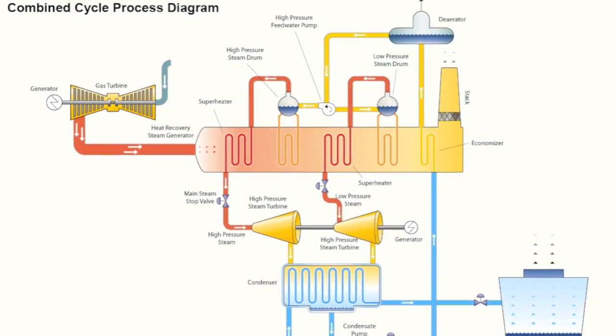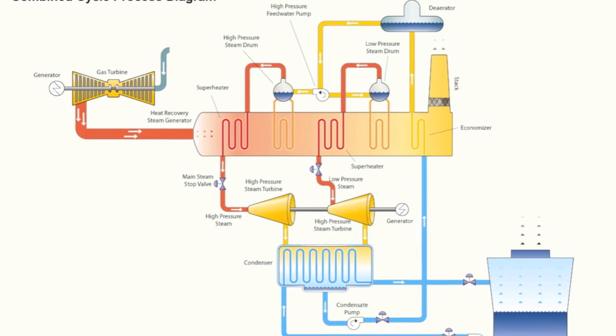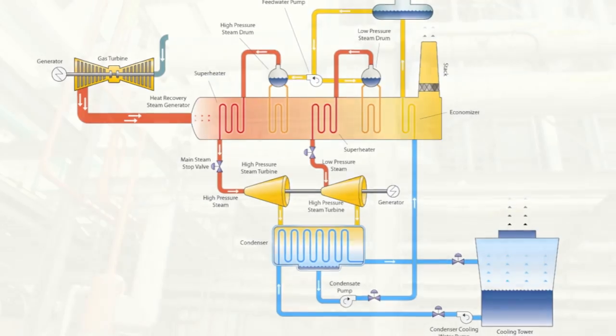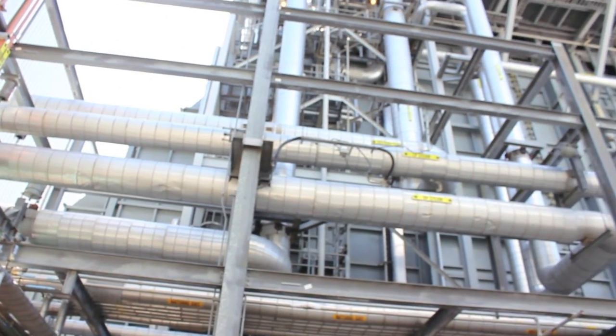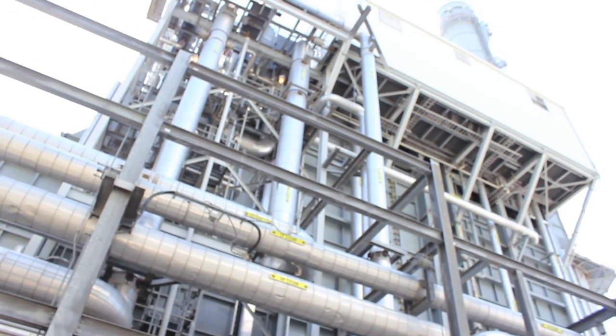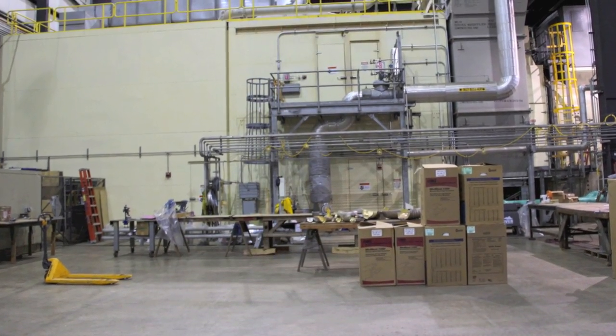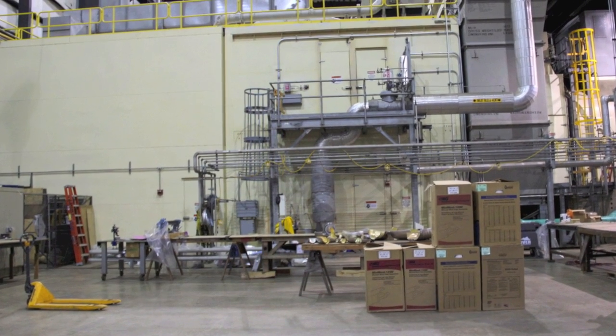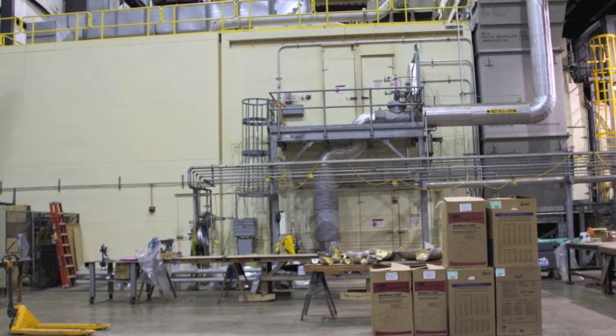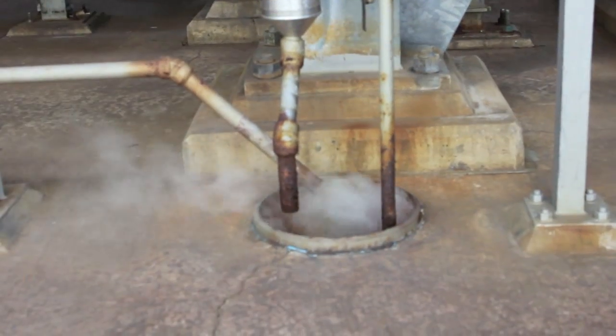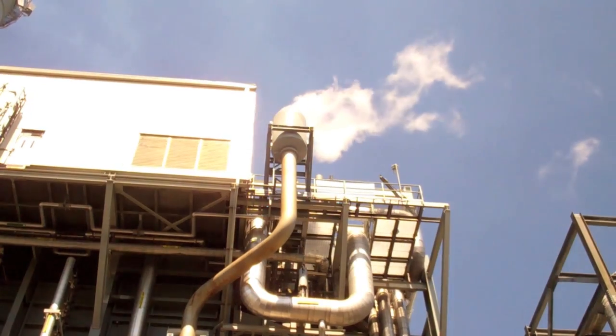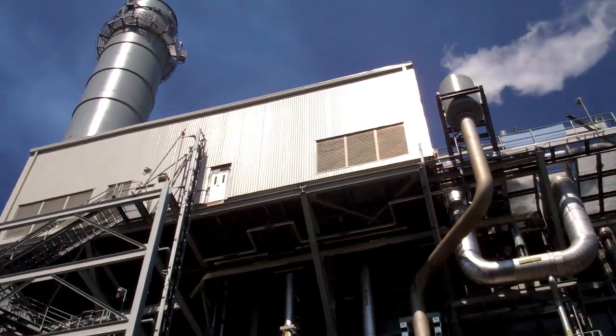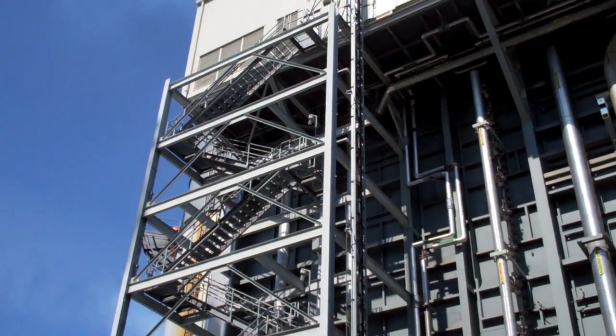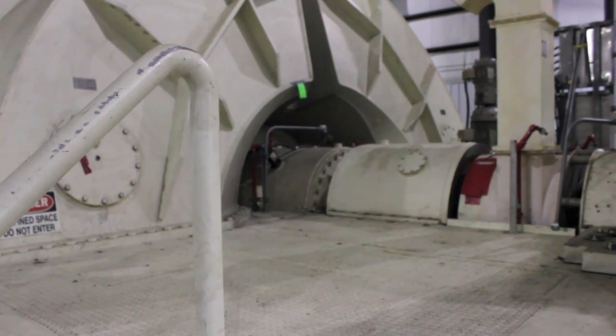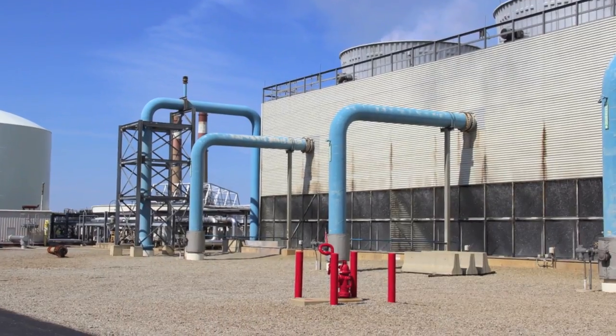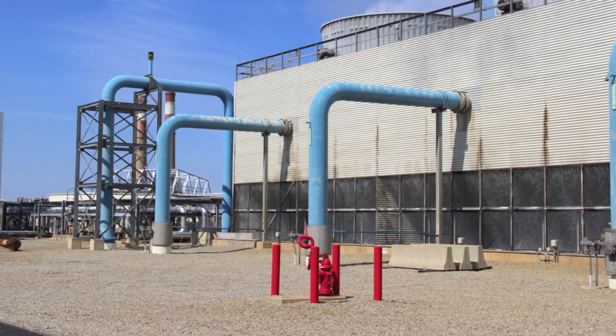The combined cycle process that we operate starts with consumption of gas in 2 General Electric gas turbines. The exhaust off of those gas turbines comes out at about 1100 degrees Fahrenheit. That hot gas comes into our heat recovery steam generator, which is basically a giant boiler. It uses all that thermal energy coming off of the gas turbines to convert water to steam. And then at the stack exhaust, our temperature is approximately 170 to 180 degrees. So the steam that's generated in our heat recovery steam generator is used in our steam turbine to produce additional power. Next, we'll move over closer to the cooling tower and let you get a better look at that.